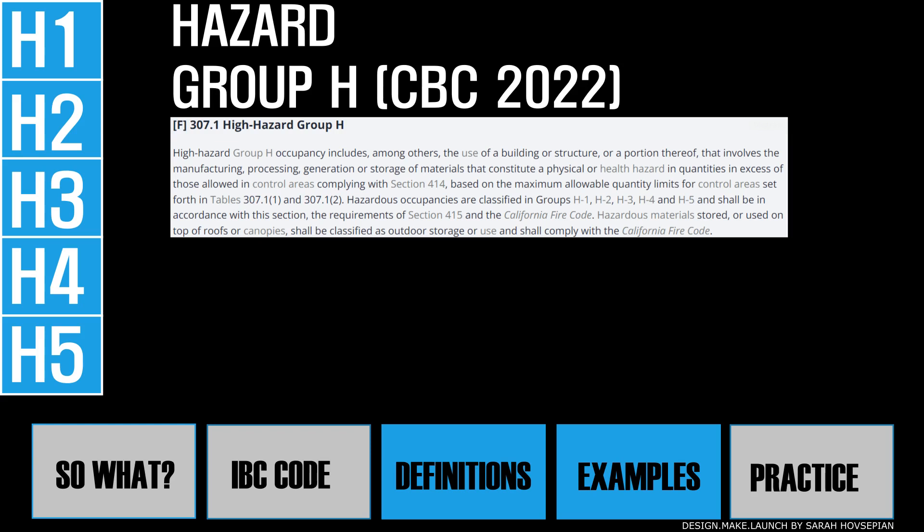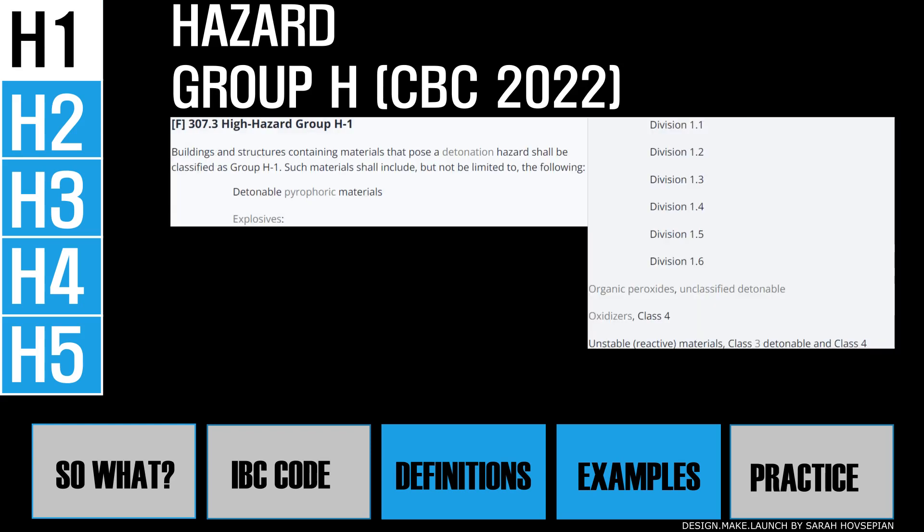Let's quickly review each one. H1 is the high hazard group — buildings or structures that contain materials that pose a detonation hazard shall be classified as group H1. Such materials include, but are not limited to, detonable pyrophoric materials. These are materials that can ignite spontaneously with the presence of air or water.